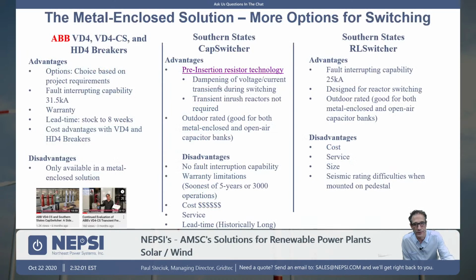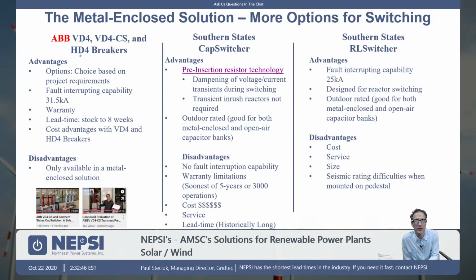This is more or less a de facto standard when it comes to the outdoor switching devices for capacitor banks. Everybody knows who they are, and I would say one of the drawbacks is lead time. Historically, it's been long, and what makes things worse is a lot of times the grid interconnect study is done late in the game, and if you have to wait till late in the game to order the switch because you don't know the size of the cap bank, it can also be one of the critical items to plant completion. So going with other switching technology, not only is there some cost advantages and lead time advantages, you can get those items on order up front because there is no resistor sizing there.